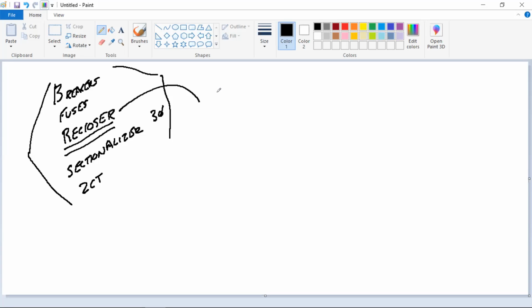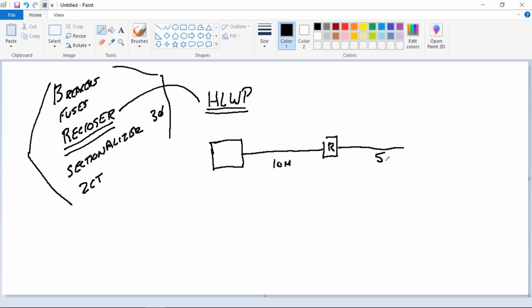The more modern reclosers nowadays, guess what they have inside? You can actually get a hotline work permit on the recloser that you're working at. That's going to be determined by the brand of recloser and all the features that it has on it. So if I have a breaker at a substation, and reclosers are usually on long sections of line, and I come out of here and I've gone 10 miles, and I put a recloser here, and then I come out of here and I've got another 5 miles, then I've got, we'll say, an open point, and then we're going to go down here to another substation. This is like Conway to Loris. If I'm working in this zone right here between the recloser and the open point, do I need to get a hotline work permit on the breaker?